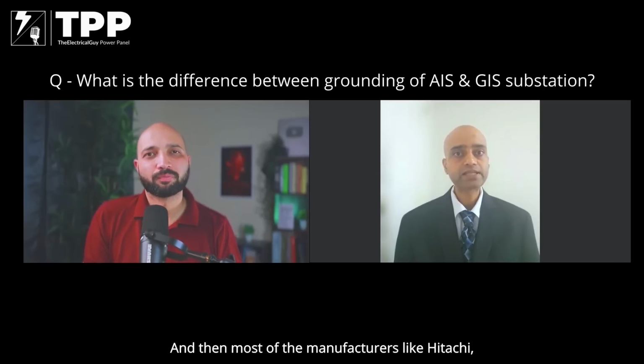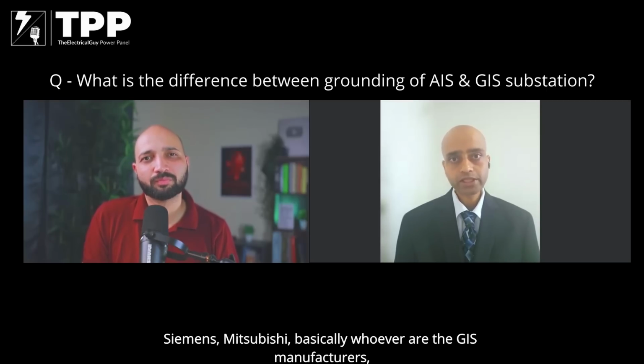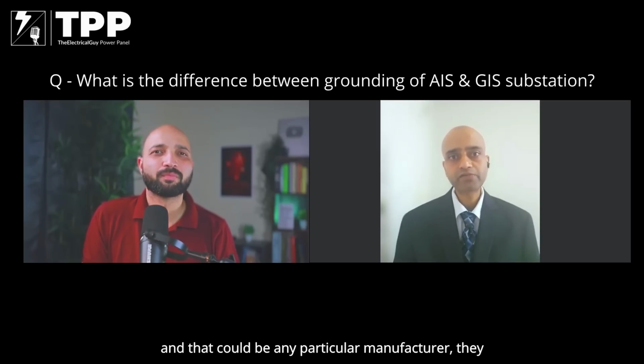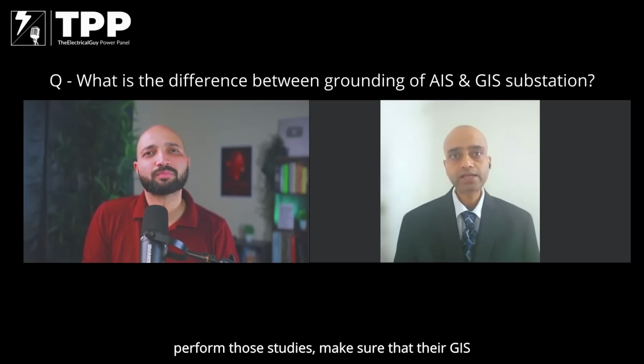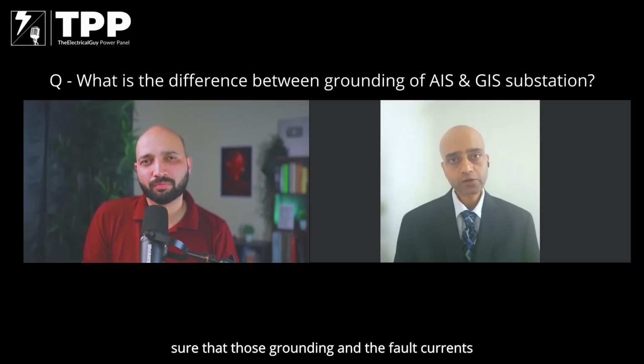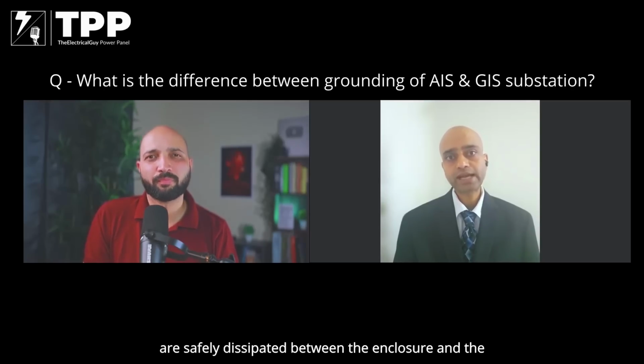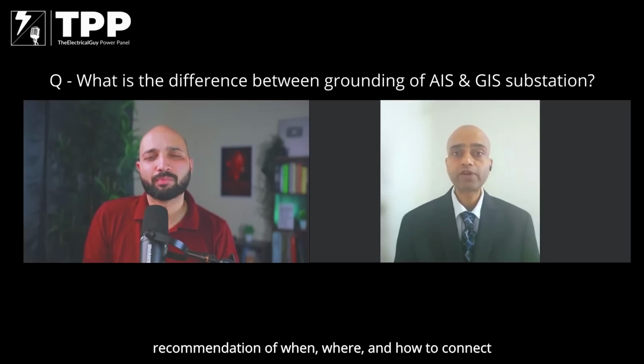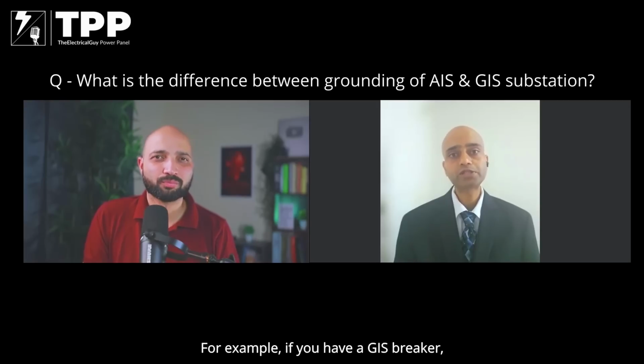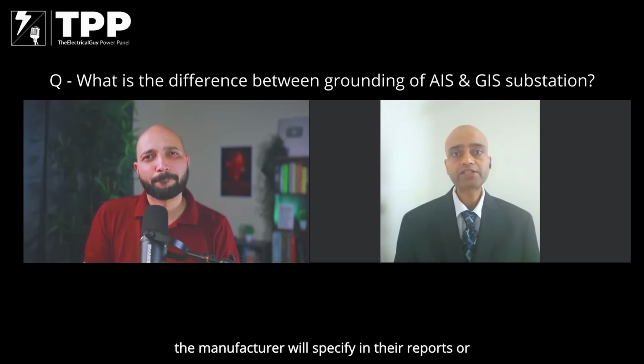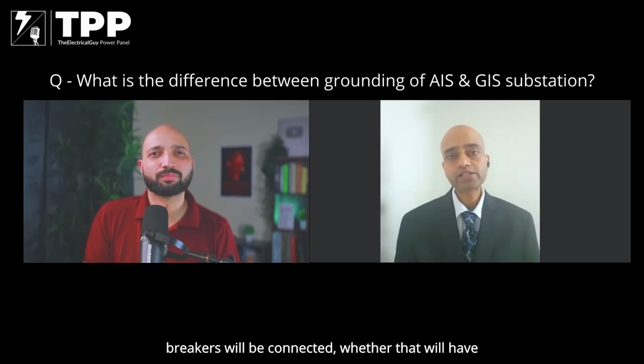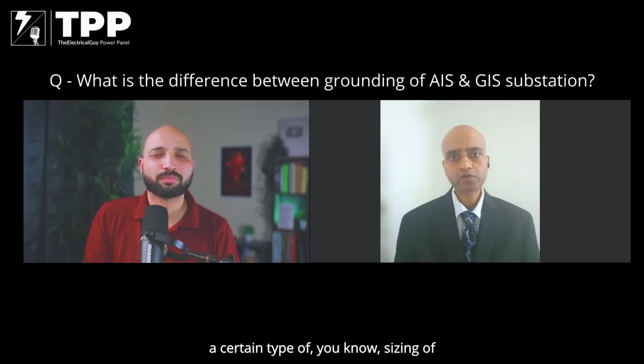Most manufacturers like Hitachi, Siemens, Mitsubishi, basically whoever are the GIS manufacturers, perform those studies to make sure that their GIS system and the building ensure grounding and fault currents are safely dissipated between the enclosure and the ground grid. They also make recommendations on when, where, and how to connect their enclosures. For example, if you have a GIS breaker, the manufacturer will specify in their reports or technical specifications how and where those breakers will be connected, the sizing of the conductor that needs to be connected to the rebar, and then rebar to the ground grid outside.